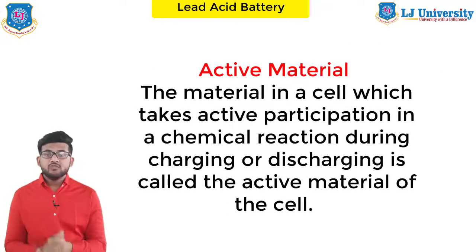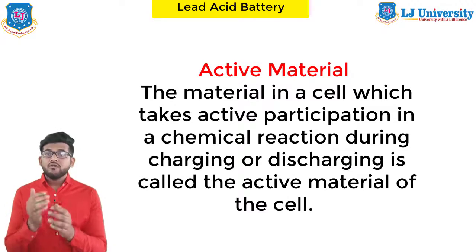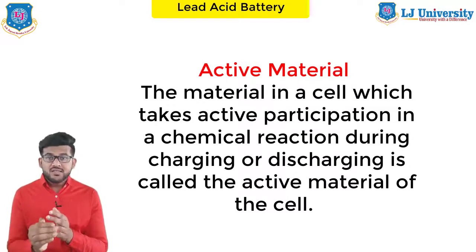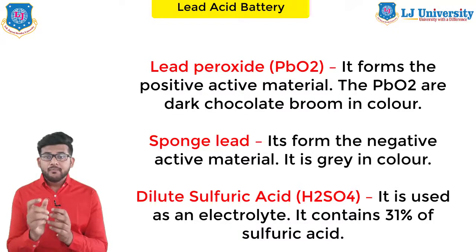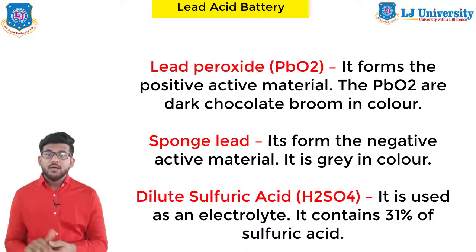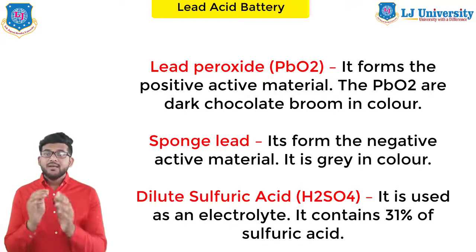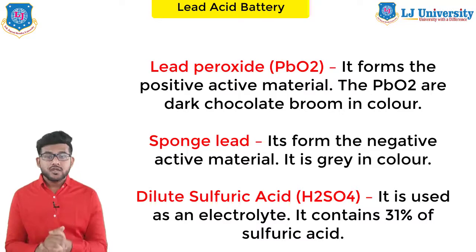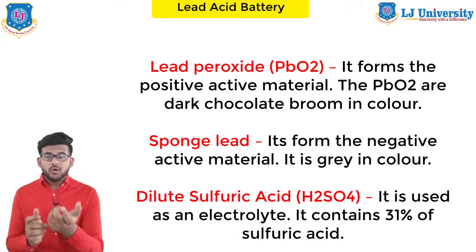Next is active material. The material in a cell which takes active participation in chemical reactions, such as absorption or evolution of electrical energy during charging or discharging, is called the active material of the cell. The active elements of the lead acid battery are: lead peroxide, PbO2, which forms the positive active material and is dark chocolate-brown in color; sponge lead, Pb, which forms the negative active material and is gray in color; and dilute sulfuric acid, H2SO4, used as the electrolyte, containing 31% sulfuric acid.